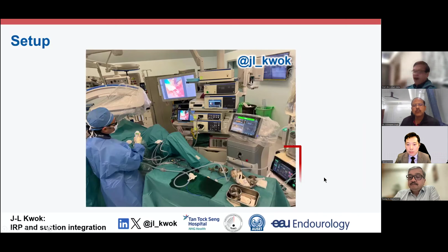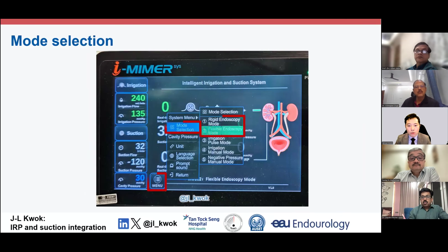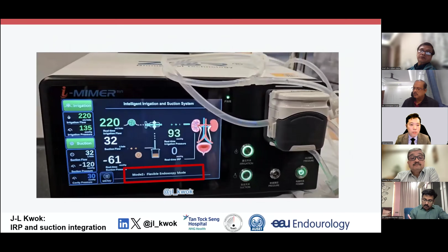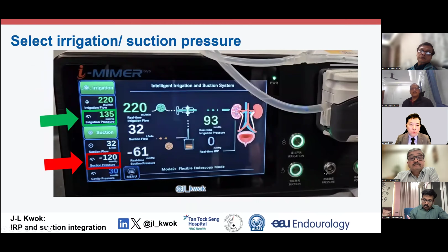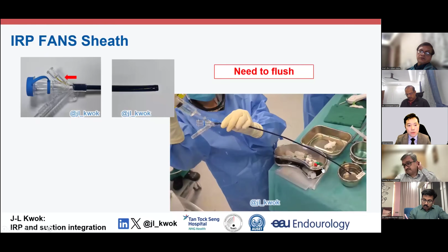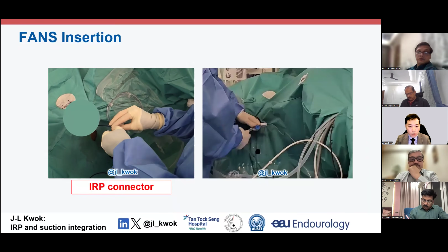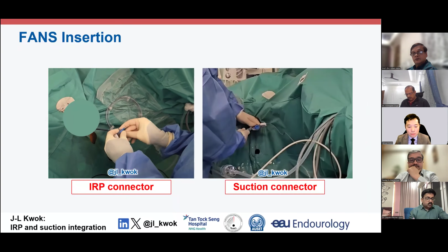So this is a setup that I use in my OR, with the pump at the side. You select the mode, the flexible endoscopy mode, and then you start it, and set the irrigation pressure and suction pressure that you like. First, you have to calibrate, or flush the sheath with water, in this case for this system. As mentioned, different systems have different kinds of calibration. Then you insert the sheath as per usual, but in this case you attach an IRP connector to this third port, and then you attach a suction port as per usual.